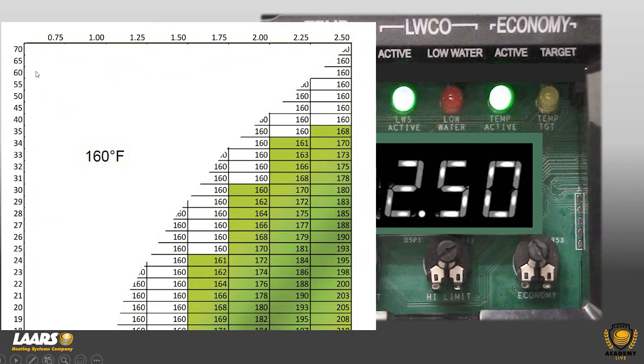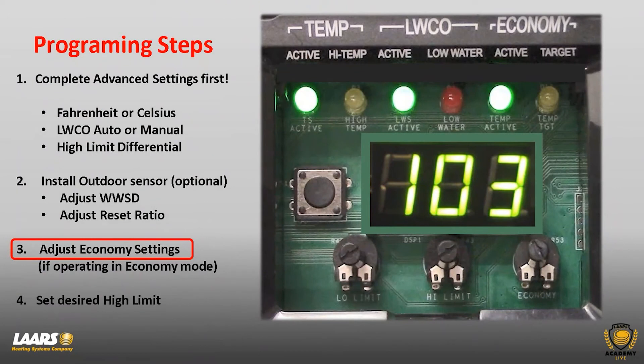Follow the chart in the manual. The left-hand column is outdoor air temperature. For example, if at 20 degrees outdoor air I want to achieve 180 degrees boiler temperature, follow that up and it gives a 2.0 reset ratio curve. Or if at 30 degrees outdoor air I want to achieve 180, that gives a 2.5 reset ratio. Make your adjustments per the manual. If you're not doing anything with step one or step two, go right to step three: adjusting economy settings for thermal targeting.